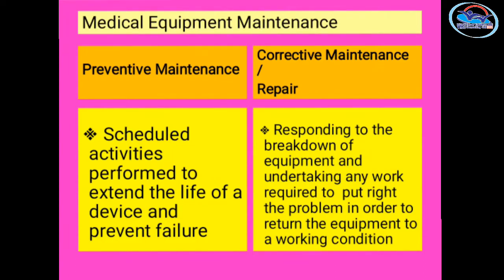Corrective Maintenance means responding to the breakdown of equipment and undertaking any work required to put right the problem, in order to return the equipment to a good working condition. When a medical equipment complaint is received, a technician works to restore the equipment to a good working condition. This process is corrective maintenance.